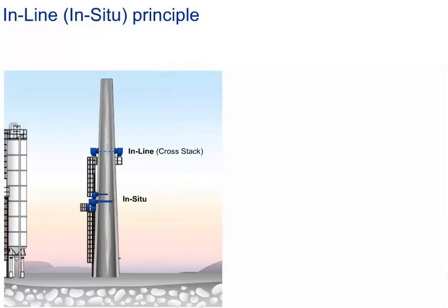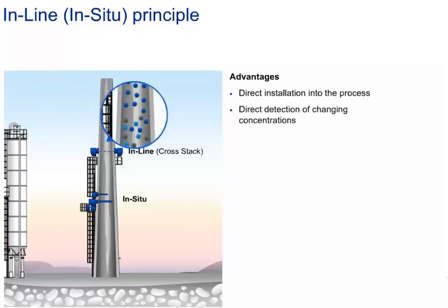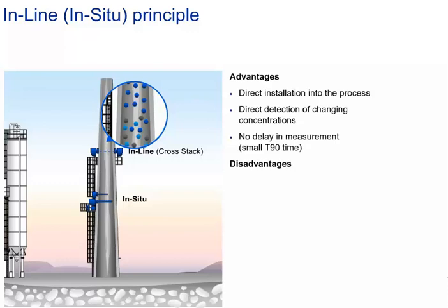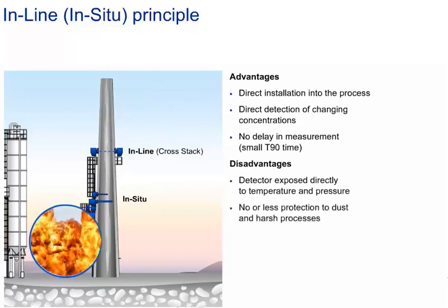Now we want to compare the methods of continuous measurement. The advantages of an in-line or in-situ measurement are: the equipment is installed directly at the process with no need for gas sample transport over longer distances, so changes in concentrations can be detected directly with no delay and only a small T90 time. But there are also some significant disadvantages: the detector is exposed directly to process conditions like temperature or high pressure, and there is no or less protection against dust and harsh process conditions.